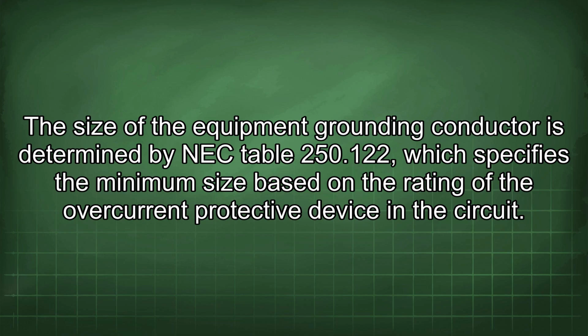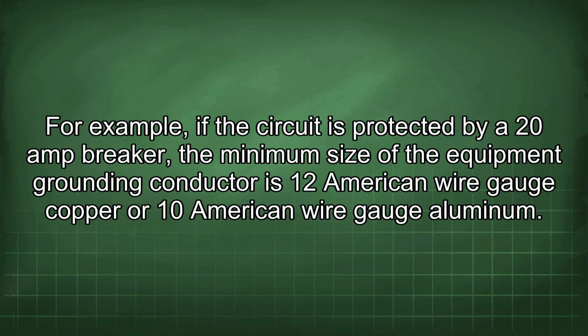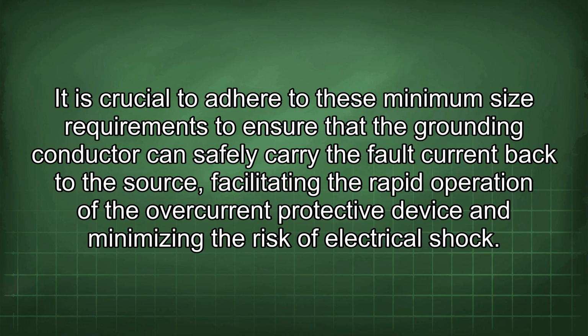The size of the equipment grounding conductor is determined by NEC Table 250.122, which specifies the minimum size based on the rating of the overcurrent protective device in the circuit. For example, if the circuit is protected by a 20 amp breaker, the minimum size of the equipment grounding conductor is 12 American wire gauge copper or 10 American wire gauge aluminum.